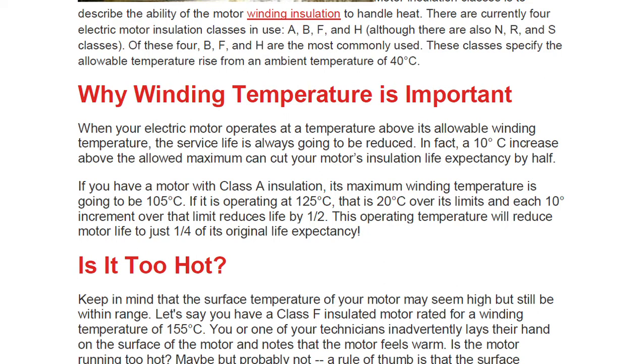When your motor is working above its allowable winding temperature, the service life is always going to be reduced. There is a rough figure: a 10°C increase above the allowed maximum can cut your motor's insulation life expectancy by half. So imagine — only a 10°C increase cuts the motor life by half.